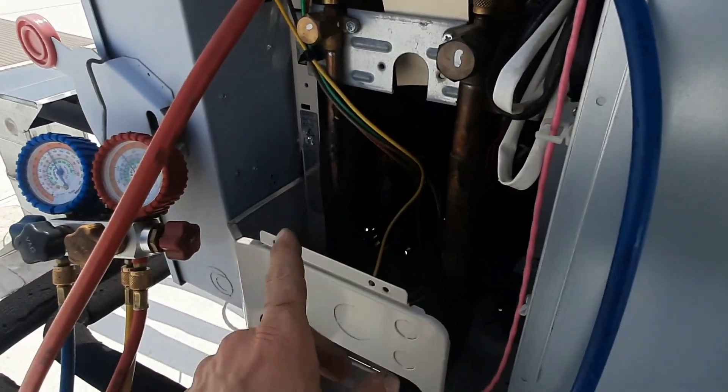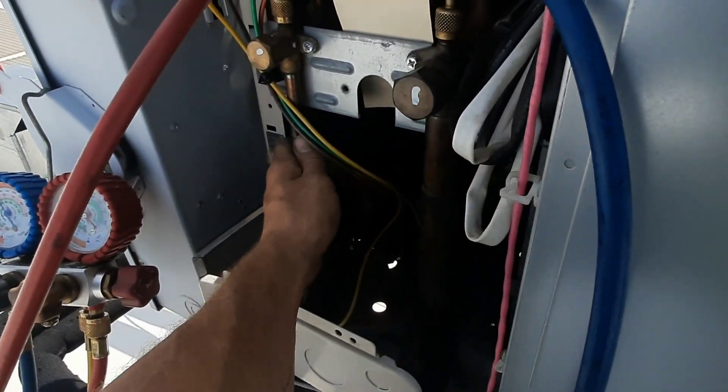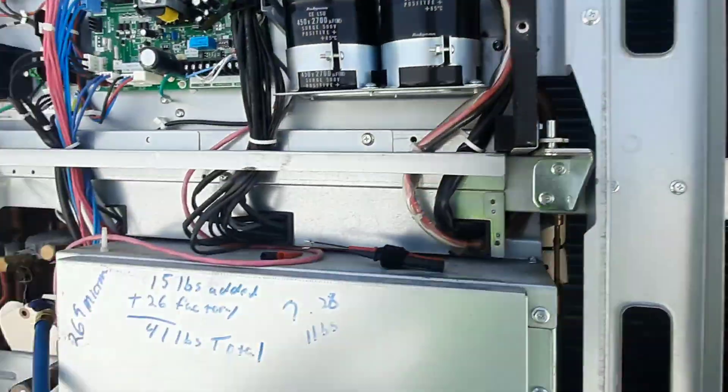You can hear the hissing has changed pitch — it's gotten less. Kind of like I'm actually getting liquid. I actually got a warm liquid line and a cold, sweaty suction line now, and my fan just kicked in.